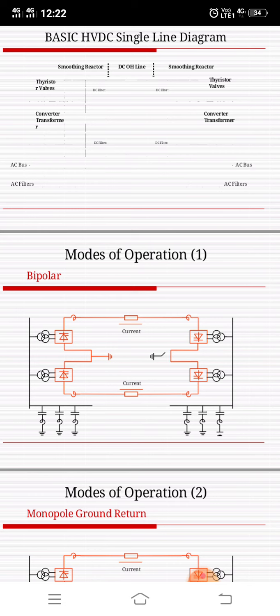During maintenance or outage of one pole, it is still possible to transmit part of the power. More than 50% of the transmission capacity can be utilized, limited by the actual overload capacity of the remaining pole.